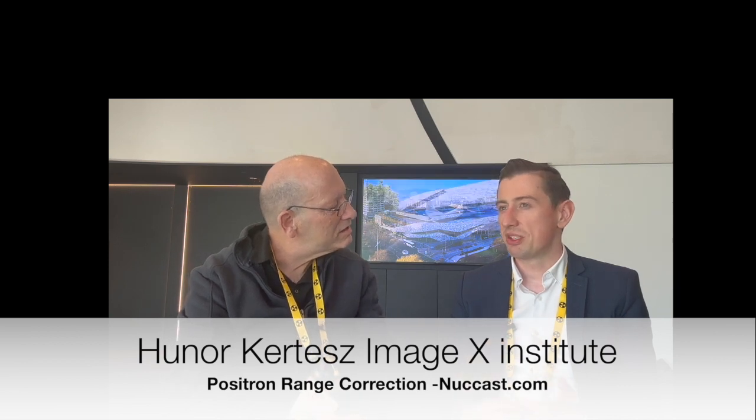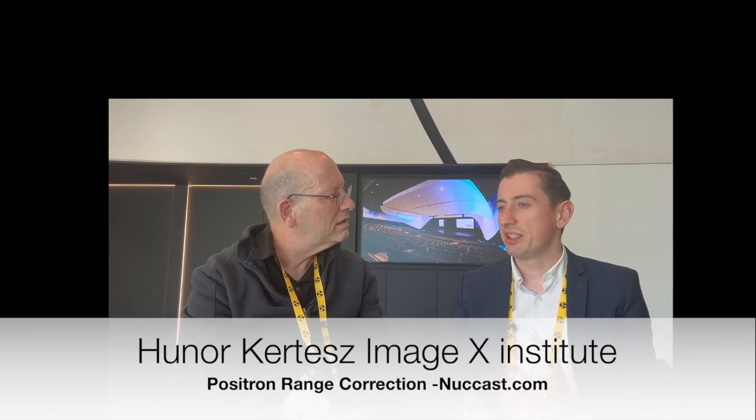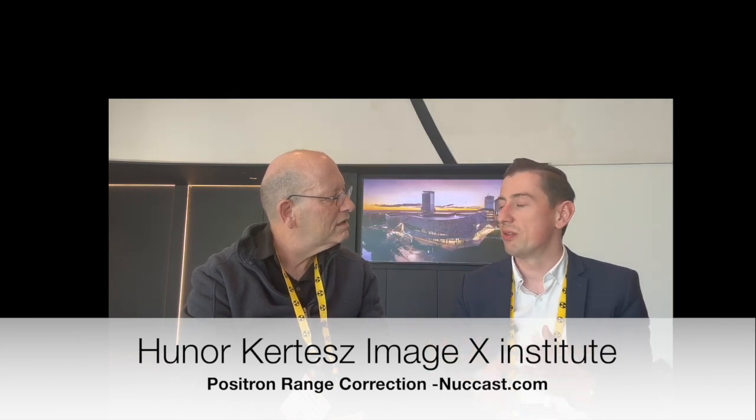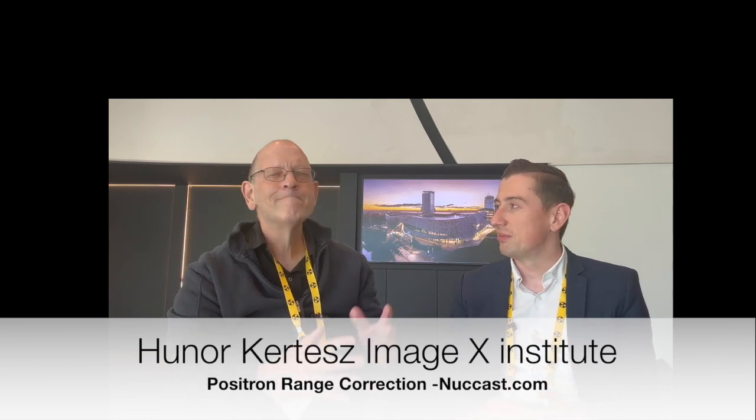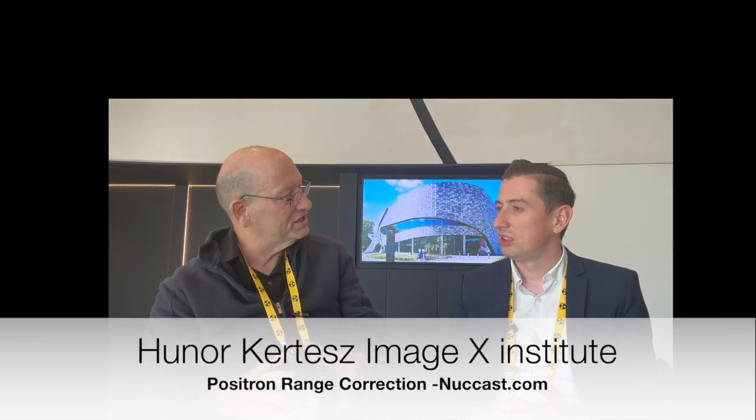The Gibbs artifact is a well-known issue from PSF. When we do positron range correction, we see the Gibbs artifacts become even more pronounced. What we can do is adjust the size of the kernels to somewhat limit the Gibbs artifacts. It mainly happens at sharp edges — we did phantom studies with a water phantom that has a really sharp border, which you usually wouldn't see inside a patient.